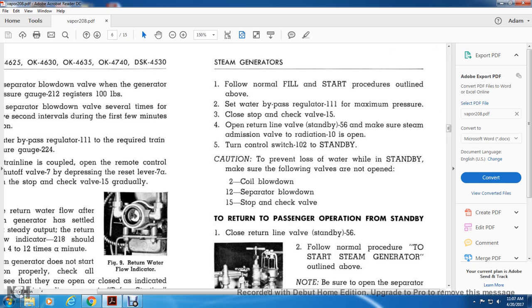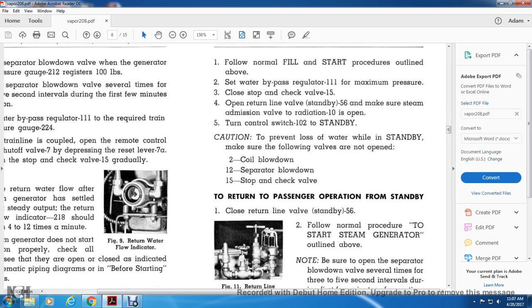Caution: to prevent loss of water while in standby, make sure the following valves are not open: 2, the coil blowdown; 12, the separator blowdown; and 15, the stop and check valve. To return to passenger operation from standby, close the return line valve standby 56. Follow normal procedure, start the steam generator as outlined above.